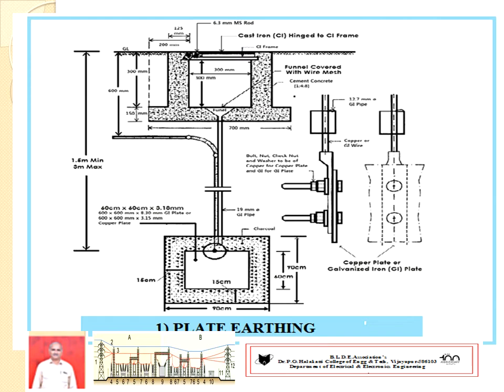So through the funnel, salt water is poured from time to time. It increases the conductivity, or it reduces the resistivity of the soil. Another GI pipe is there at the side. Through this GI pipe, the earth wire is connected from the building meter board to the earth electrode, and by using nut and bolt arrangement, it is fixed as shown in the side figure. If copper plate is used, then copper nut and bolts are used. If GI plate is used, then GI nut and bolts are used as shown in figure.